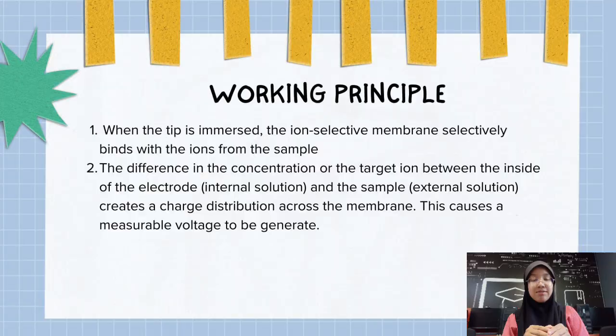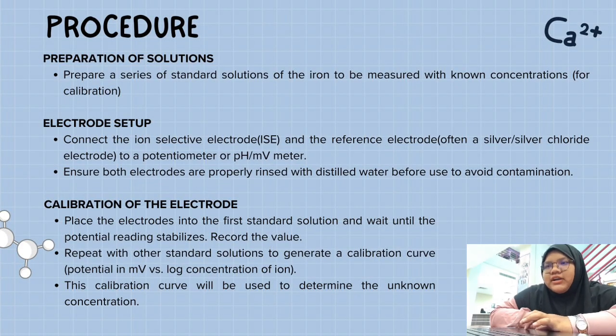Let's go to the procedure. Okay, procedure for ion-selective electrode. Firstly is preparation of solution. Prepare a series of standard solutions of the ion to be measured with known concentration for calibration. And then electrode setup. Connect the ion-selective electrode, ISE, and reference electrode, often a silver or silver chloride electrode, to a potentiometer or pH or mV meter. Ensure both electrodes are properly rinsed with distilled water before use to avoid contamination.